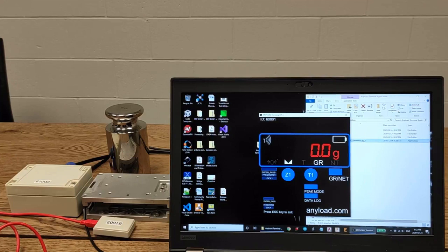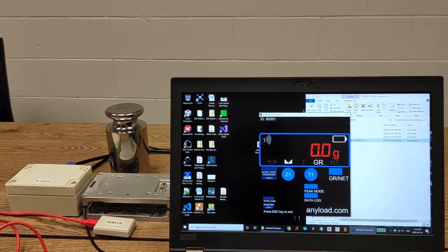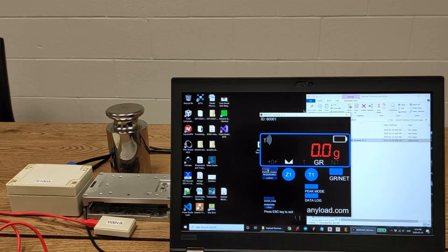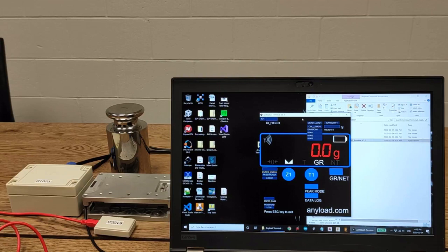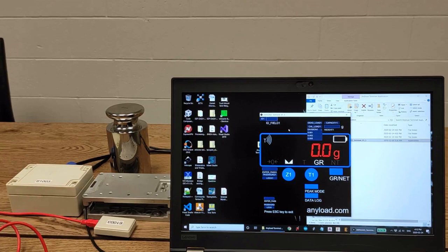Now, since this is the initial setup, the ID field needs to be checked and corrected. To do that, you will enter the password and the calibration parameters will show up.